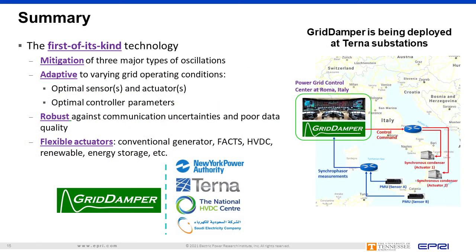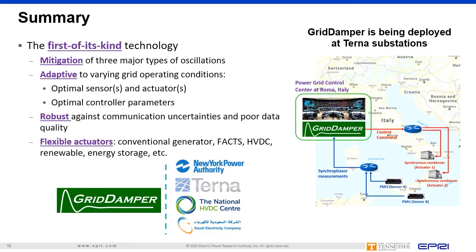Grid Damper is the first of its kind technology that can mitigate all three major types of oscillations while also having the adaptive capability to handle varying grid operating conditions. It is robust against communication uncertainties and has the flexibility to work with various kinds of actuators. Grid Damper has been successfully implemented on hardware and tested on four realistic power grids: the New York Power Authority in the US, Terna in Italy, the National HVDC Center in the UK, and the Saudi Electricity Company in Saudi Arabia. Field deployment is happening right now in the control center of the Italian transmission system operator, Terna.